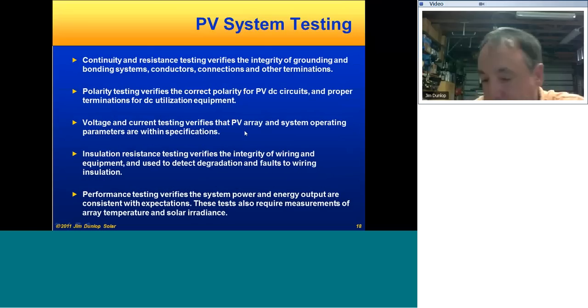So there are several types of tests that can be done to verify a lot of the code requirements. There's continuity resistance testing, to verify all the grounding and bonding connections, terminations, ground resistance, and polarity testing, as well as voltage and current testing, to verify correct phasing, polarity, and values within the specifications for the system. And insulation resistance testing is going to verify the integrity of the wiring, equipment, terminations, and so forth. It can be used to detect faults in the system as well, which we'll talk about here in a minute.